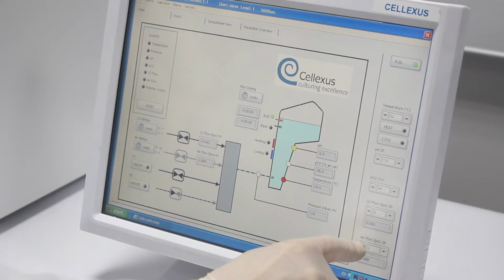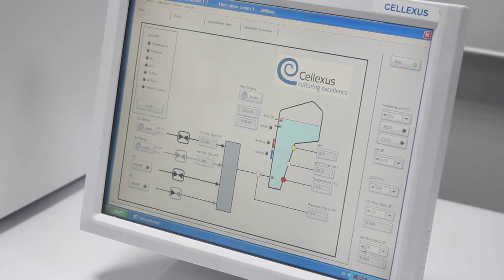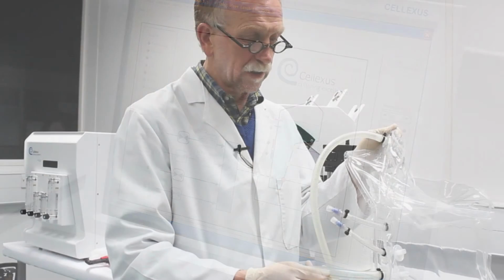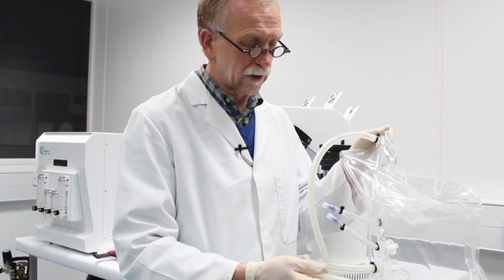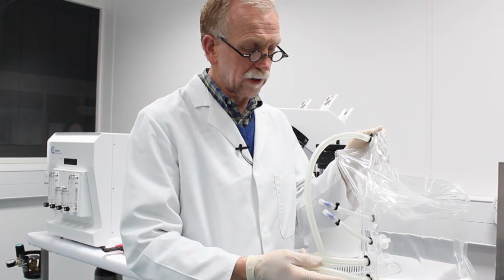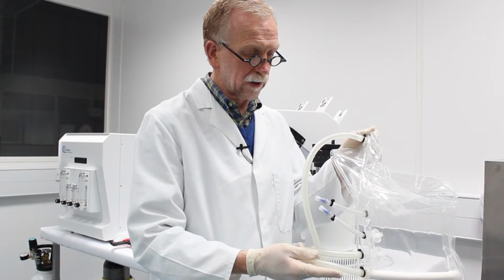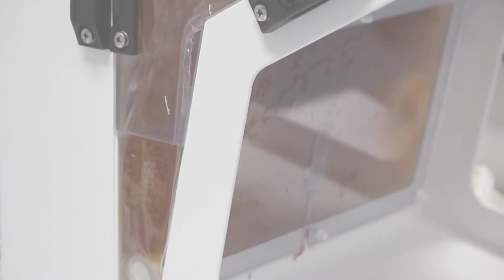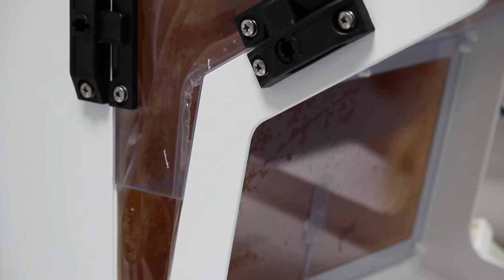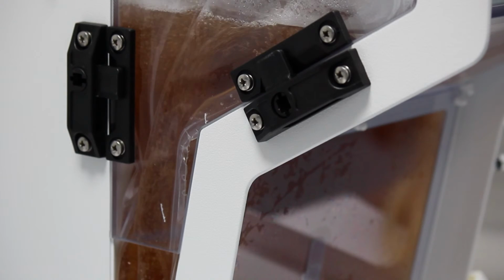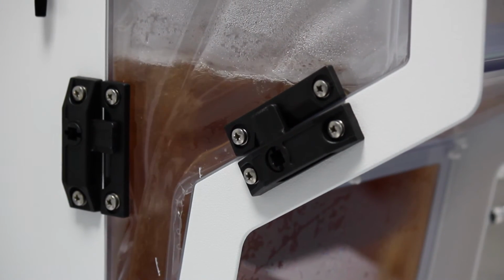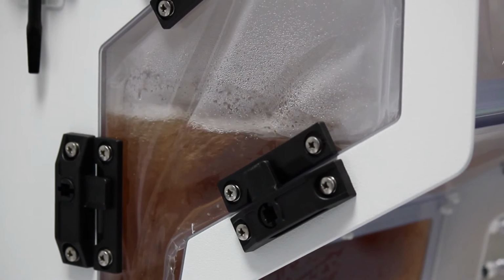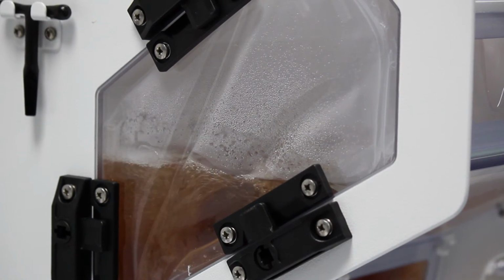Up to 10 litres a minute of air can be delivered to the Cellmaker bag and up to 4 litres of oxygen. On the Cellmaker Plus, oxygen flow is automatically controlled by monitoring of the DO using the integrated DO sensor in the Cellmaker Plus bag, such that if oxygen levels fall below the user-defined levels, oxygen will be added to ensure that that level is at least maintained. Air supply to the headspace at the top of the bag helps to increase gas exchange and reduce foaming. The vent regulates the flow of the exhaust gases and dictates the overall pressure in the Cellmaker bag.